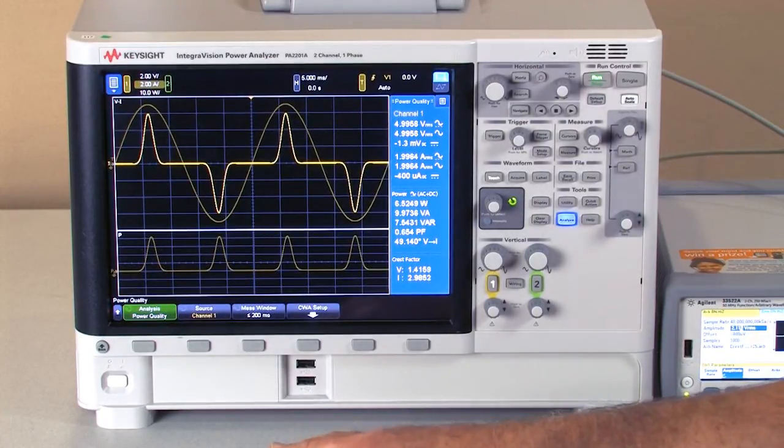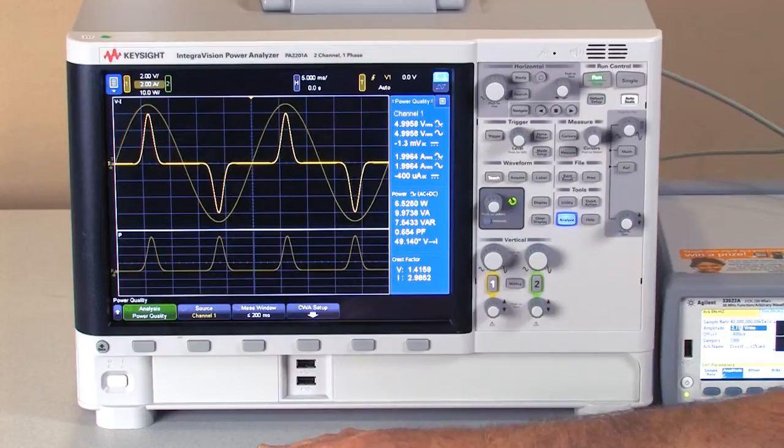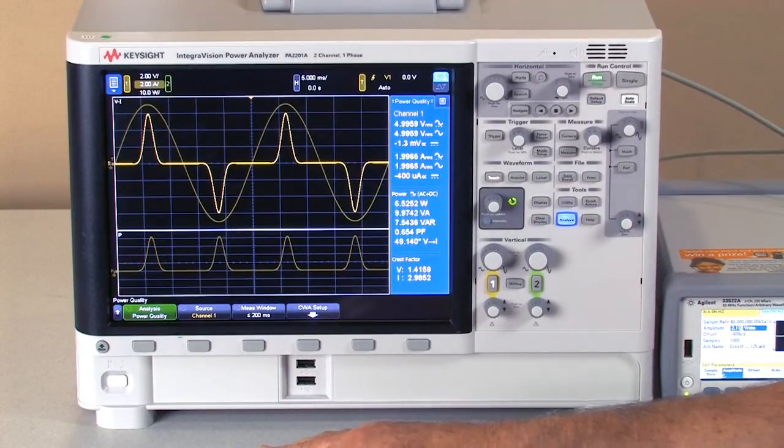If you remember, crest factor is defined as the ratio of the peak to RMS value of the signal. The PA2201A can actually measure crest factors of up to 3 on a full-scale signal.